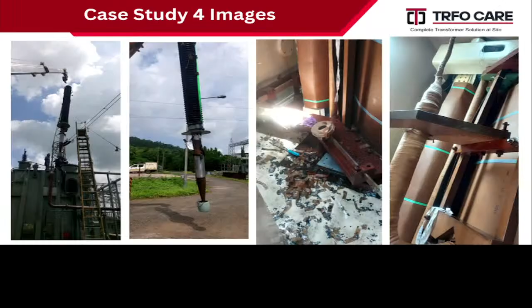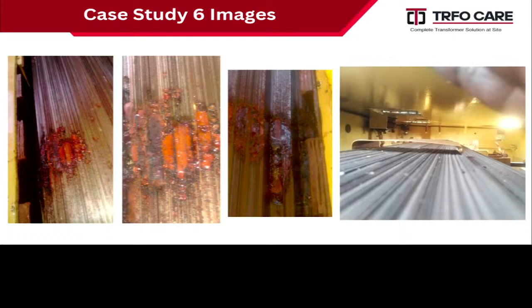So these are the different cases. This is a special case: no acetylene, nothing, only ethylene and ethane gas observed on this particular transformer. See the heavy rusting of the core. Because of the rusting of the core, we found more ethylene on this transformer. So we rectified at the site, cleaned the core properly. Now for the last 2 years, no gas rising in this transformer. So these are the various types of case studies.